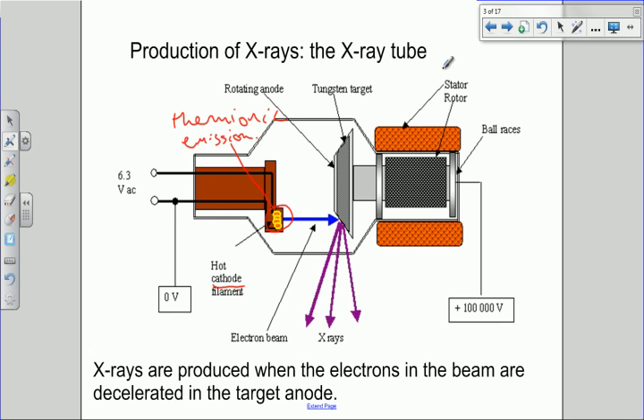The electrons get emitted from that wire and then they zoom across the gap here. This gap is actually evacuated. That's a vacuum. So there's no air in here. If there was air in here, the electrons would hit the air molecules on their way across and lose lots of kinetic energy and probably most of them wouldn't make it at all. So we take all the air out in order to facilitate their passage across this little gap. This blue line represents the electron beam.